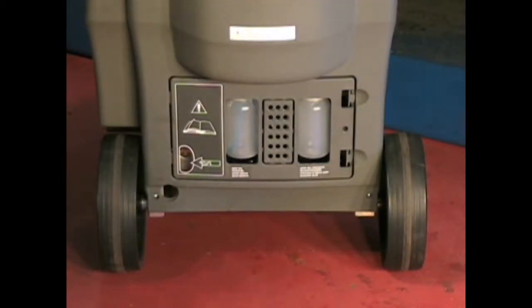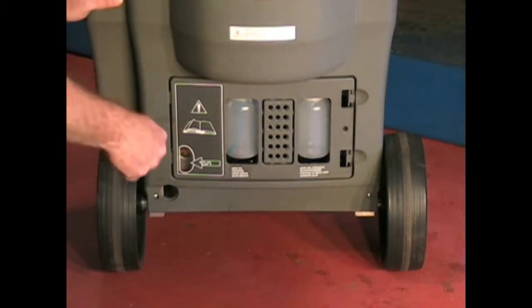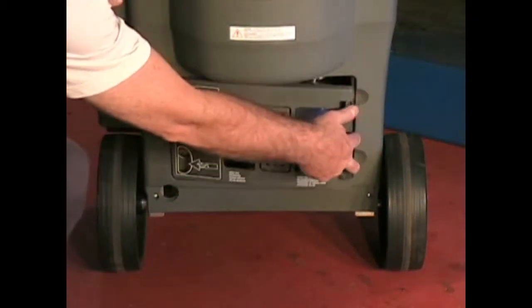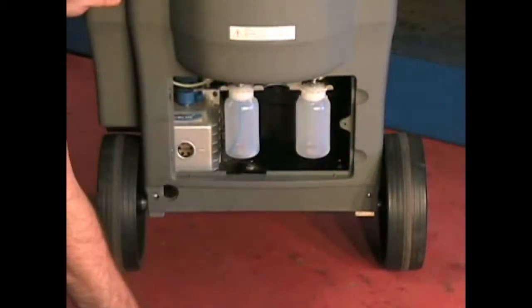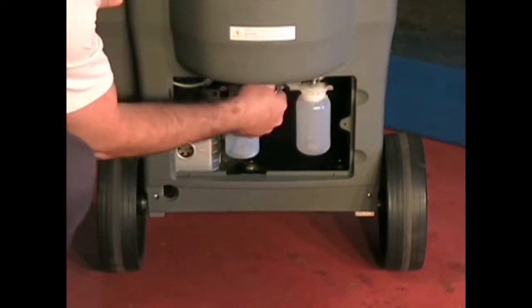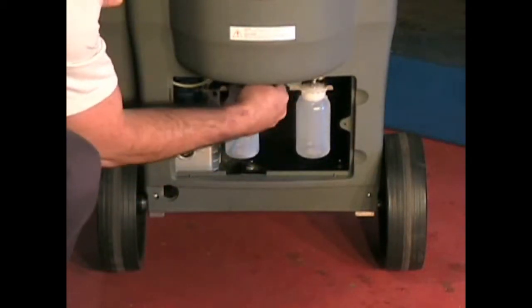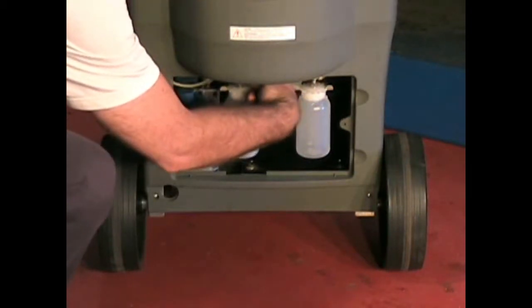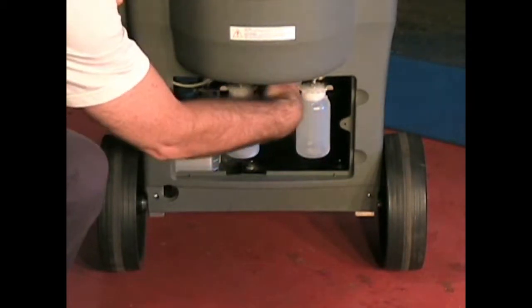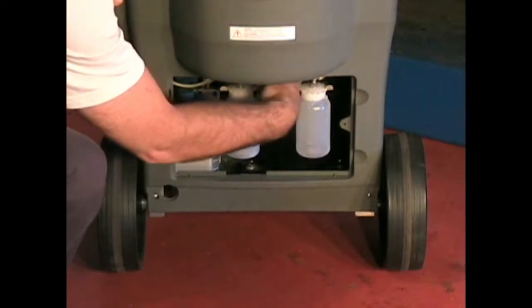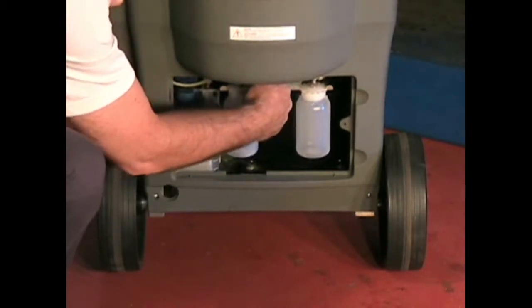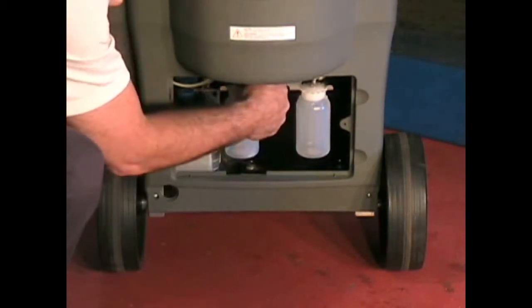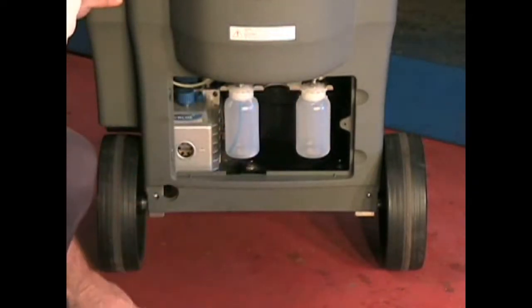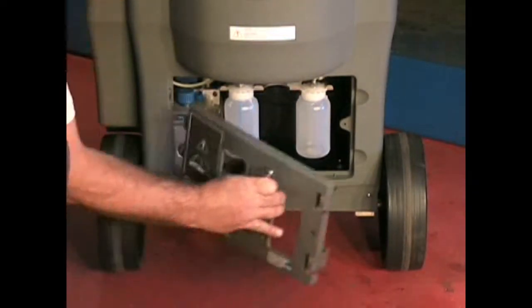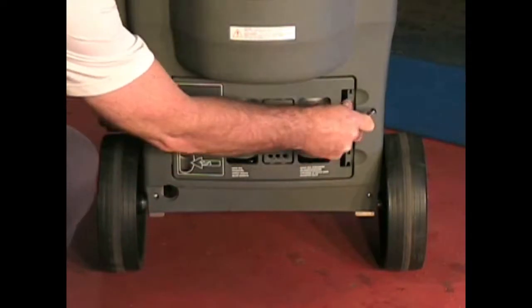To set up your new CCST388, start by backing out the scale travel pin. Remove the lower back cover and find the 10 mm locking nut in the center and behind the oil discharge and new oil bottles. Use a 10 mm wrench to unlock the nut and then back the 10 mm bolt out about 7 to 8 full turns.